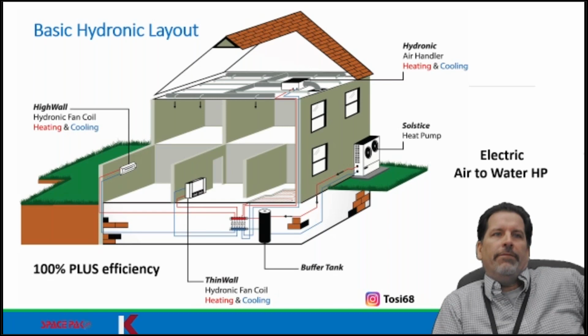We're barely achieving the efficiencies of what the yellow label says for condensing wall products, let alone cast iron, which is now an atmospheric vent versus some kind of fan assist, right? Think about an electric water heater. The concept is energy in, heat out, 100%, no loss. Maybe thermal, just because of standby, right? Insulation of the tank and things of that nature.